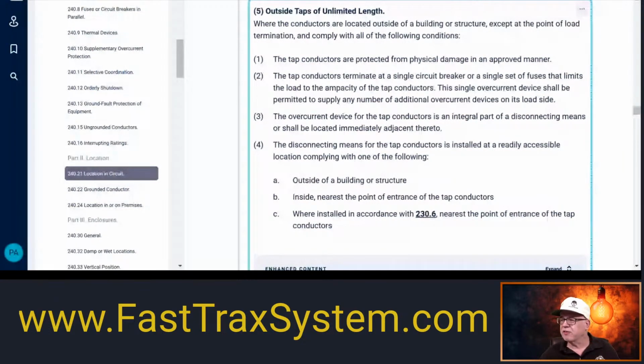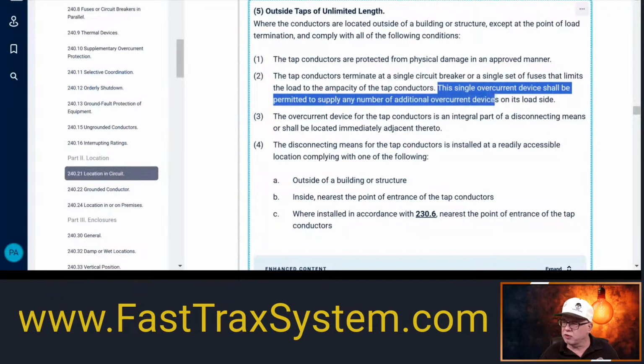Okay. Next, it says the single overcurrent device shall be permitted to supply any number of additional overcurrent devices on the load side. So that means it could hit a main breaker and then you have other overcurrent devices on the load side. That's perfectly fine. Or you could hit a single main disconnect, right? And then it has additional overcurrents on the load side of it, and that's fine also. Doesn't matter whether they're together in one cabinet or two separate cabinets. It doesn't really matter. And I had an illustration I could show of that, but that's kind of what we're talking about.